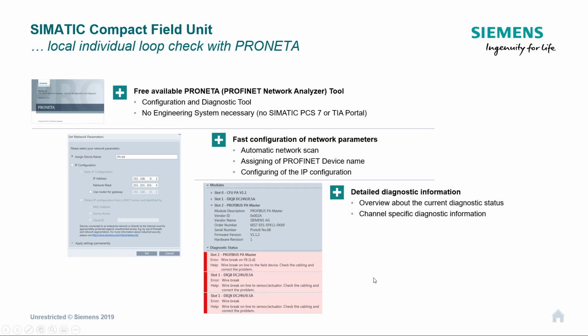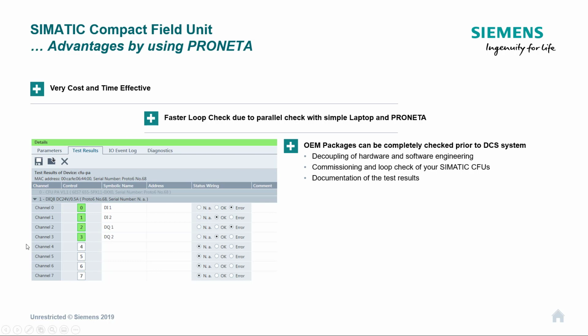So quite a nice powerful tool if you're not connected to a DCS or a PLC. You can connect all of your instruments up to the Compact Field Unit. They'll automatically address, they'll start assigning the generic GSDs, and you'll have the diagnostics on that channel. There's another screenshot here. So this is showing you the digital inputs. I believe you can't do any configuration with PRONETA on the digital and the Profibus signals, because you don't really want to override the connection to the DCS or the PLC. That would be quite dangerous, but as a diagnostic tool it's fantastic.